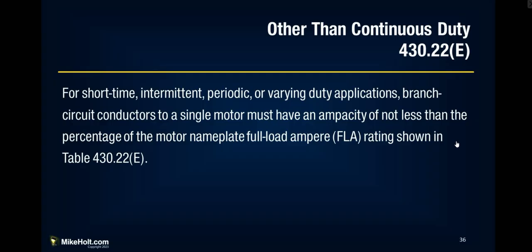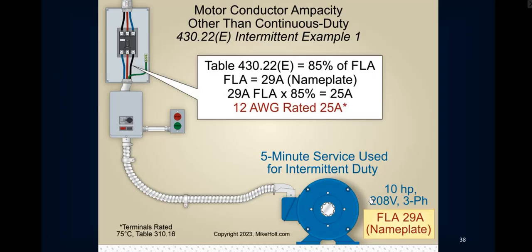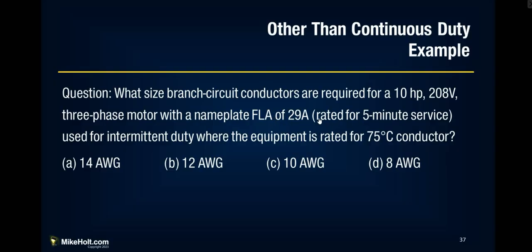For short-time, intermittent, periodic, or varying duty applications, branch circuit conductors to a single motor must have an ampacity of not less than the percentage of the motor nameplate FLA rating shown in 430.22(E). So now, I'm going to skip to this one here. Other than continuous duty, where did this 85% come from? Well, if you flip over in 430.22(E), duty cycle, 85%. Well, where'd that 85% come from? If you look back in their question, they say it is a nameplate FLA of 29 amps, rated for 5-minute service, used for intermittent duty where the equipment is rated for 75 degrees Celsius. So that tells me, if you look in that table in 430.22(E), it says the nameplate current rating percentages, and you have a 5-minute service. Well, there it is right there, 5-minute rated motor.